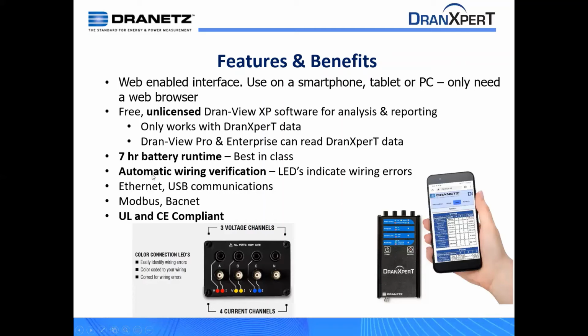Each meter comes with Ethernet and USB communications. The primary communications are Ethernet. You can control the meter, download data from the meter. USB is used for a jump drive that you can pop into the meter and have data be downloaded to that jump drive, to then bring to your computer and analyze with DranView software.